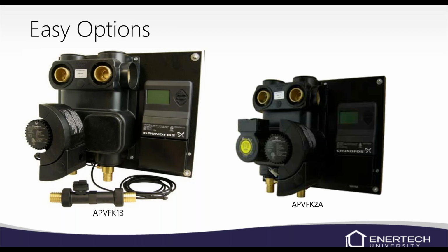One thing I will tell you guys: if you ever go out to the system and the controller is blank, it's not coming on, and obviously the pump's not going to run, and you need to get them heating or cooling, unplug the low voltage harness on a variable speed pump. The pump doesn't know what to do, so it runs at 100%. So that's a good fail-safe. I wish they would do that on the ECM blower motors, because it's never the motor that fails, it's always the module. It seems that way on these flow centers, the pumps as well, unless you hit them with a lot of air, then they're going to lock up. But normally it's the module. So just unplug the low voltage, the pump will run 100%, and then we can get you a new controller or whatever you may need.